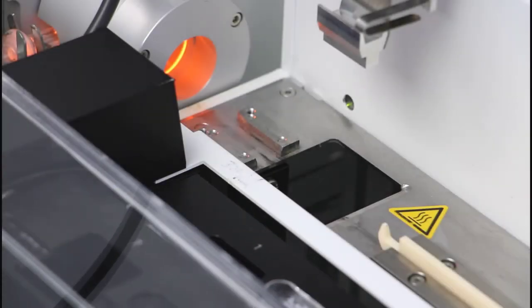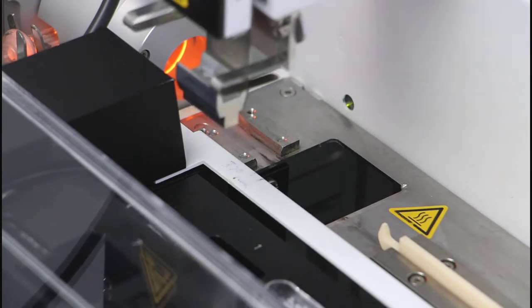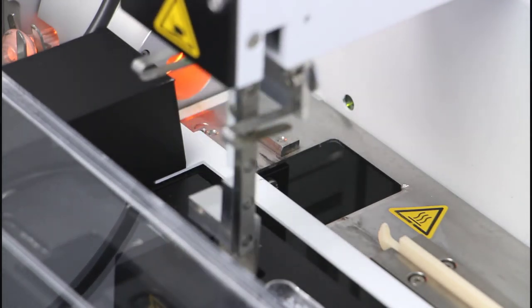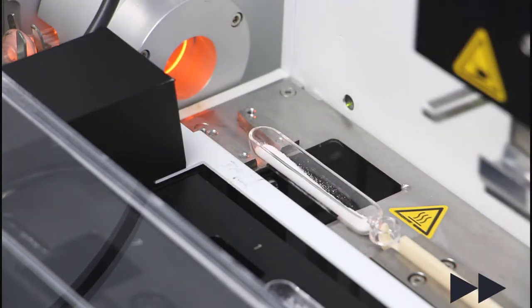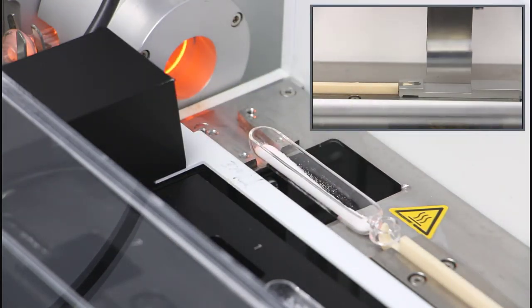Placed boats on the auto-sampler will be taken by the sampler head and positioned on the ceramic hook for introduction. The head will move into the sliding position. And after the baseline setting, the introduction starts.